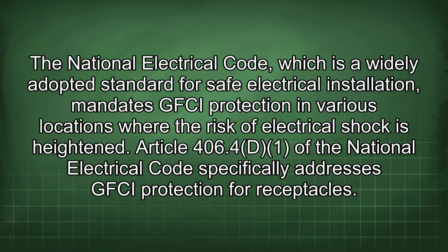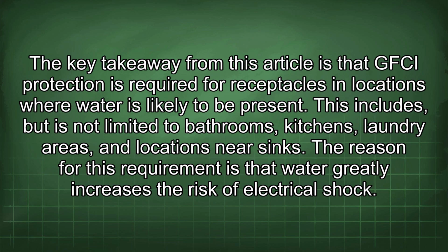The National Electrical Code, which is a widely adopted standard for safe electrical installation, mandates GFCI protection in various locations where the risk of electrical shock is heightened. Article 406.4 of the National Electrical Code specifically addresses GFCI protection for receptacles. The key takeaway from this article is that GFCI protection is required for receptacles in locations where water is likely to be present. This includes, but is not limited to, bathrooms, kitchens, laundry areas, and locations near sinks.